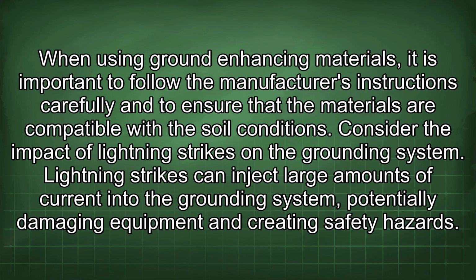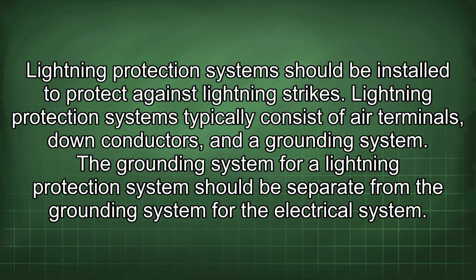Consider the impact of lightning strikes on the grounding system. Lightning strikes can inject large amounts of current into the grounding system, potentially damaging equipment and creating safety hazards. Lightning protection systems should be installed to protect against lightning strikes. Lightning protection systems typically consist of air terminals, down conductors, and a grounding system. The grounding system for a lightning protection system should be separate from the grounding system for the electrical system.